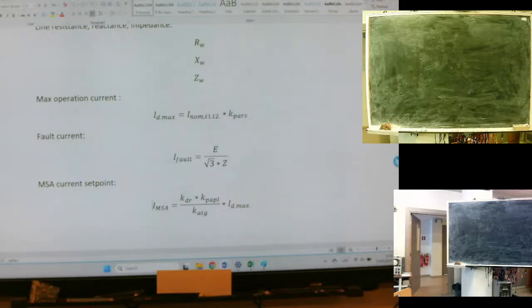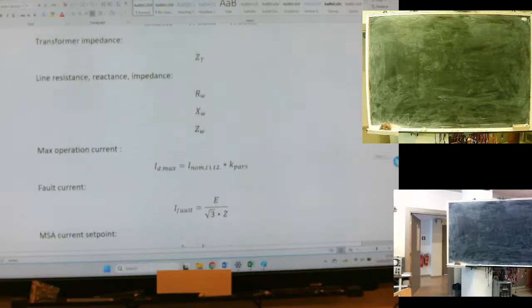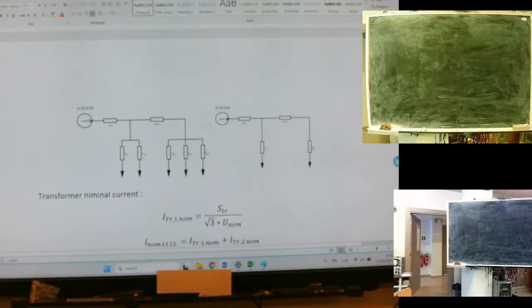One very important moment. If we calculate this fault value, what is that value? What is the full impedance? This is quite important, because for fault calculation in this type of network the formula is very simple, but based on where we put the fault, the impedance is the full way from the source to the fault location.